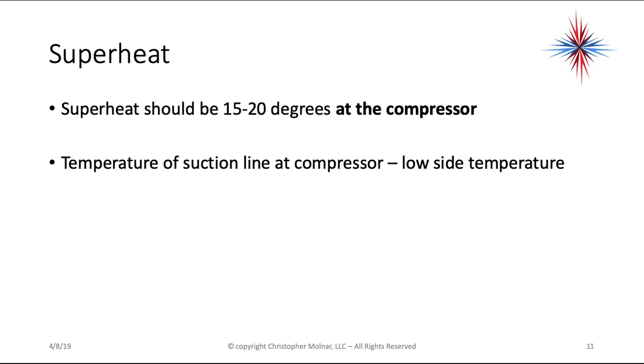Superheat should be between 15 to 20 degrees at the compressor. Now, someone out there might say superheat should be 8 to 12 degrees — there's a difference between system superheat and evaporator superheat. This is one of those numbers that, based on the efficiency of your equipment and what expansion device you're using — a fixed orifice or a TXV — can change a little bit. It's going to be lower with higher efficiency equipment. To get superheat, look at the temperature of the suction line at the compressor, minus the low side temperature.